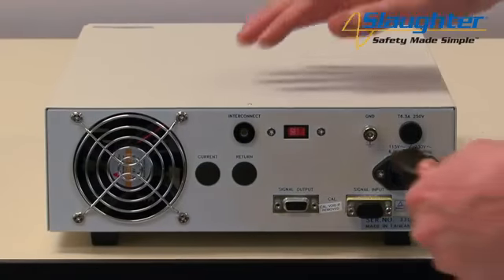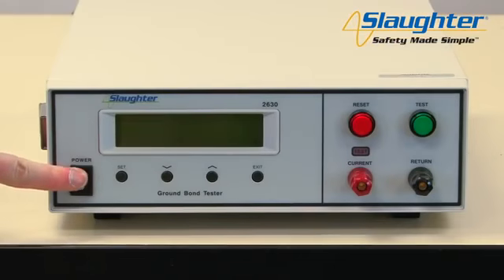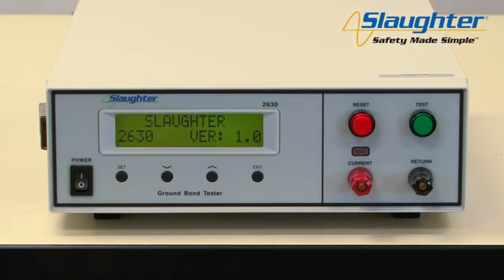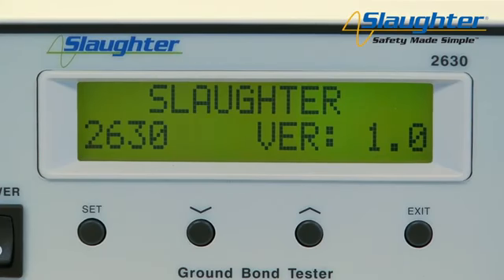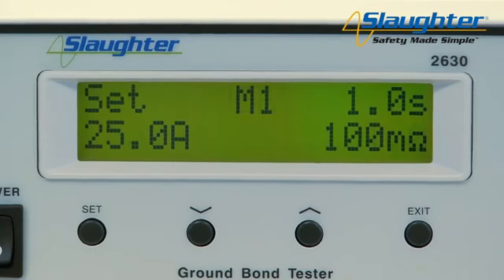Connect the power input plug into its socket on the rear panel of the tester. Connect the male end of the plug to the outlet receptacle. Now, turn on the power switch on the front panel of the 2630. On the startup screen, you will see the company name, model number, and firmware version. From here, the tester will automatically navigate to the Perform Test screen. The Perform Test screen displays 5 parameters: status indicator, memory number, test time, test current, resistance limit.